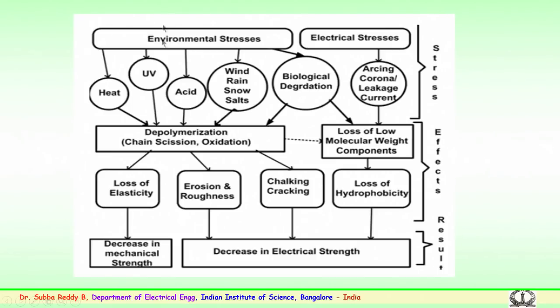So you see the various environmental and electrical stresses here, and the effects from these are given here, along with the final result. When you see the final result, the insulation strength could come down and a flashover could happen, or mechanically it could become unstable, where the insulator string can fail because of brittle fracture, or the rubber could peel off from the insulator surface. These are very important concerns, and polymeric or composite insulators require a lot of regular maintenance.